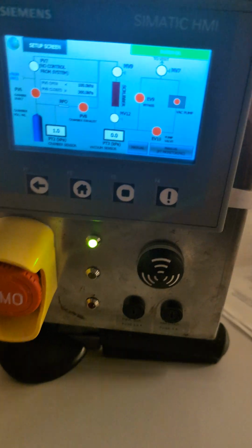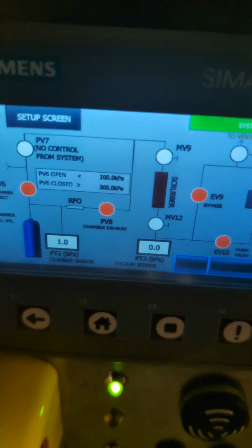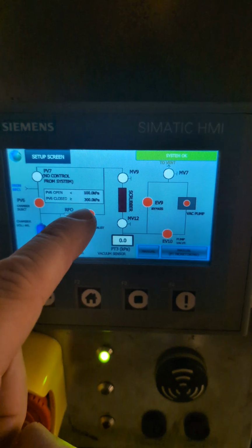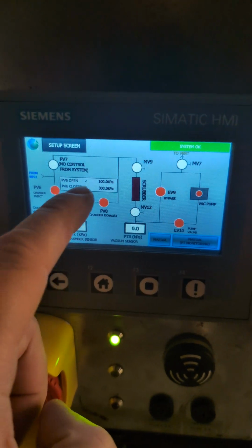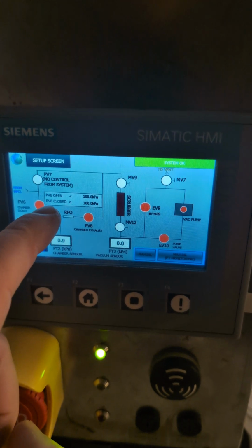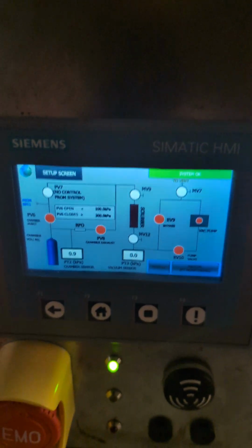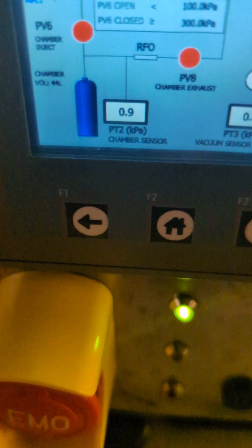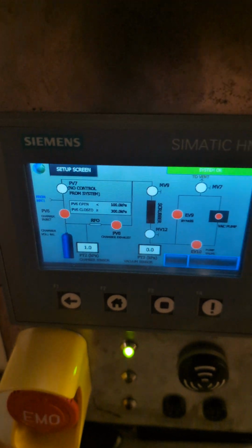So we go back to the P&ID screen and you'd see here that it's changed. You'd see 100 to 300, so PV6 opens if it's less than 100 kPa, and PV6 closes when it goes over 300 kPa. This is the pressure transducer, PT2.